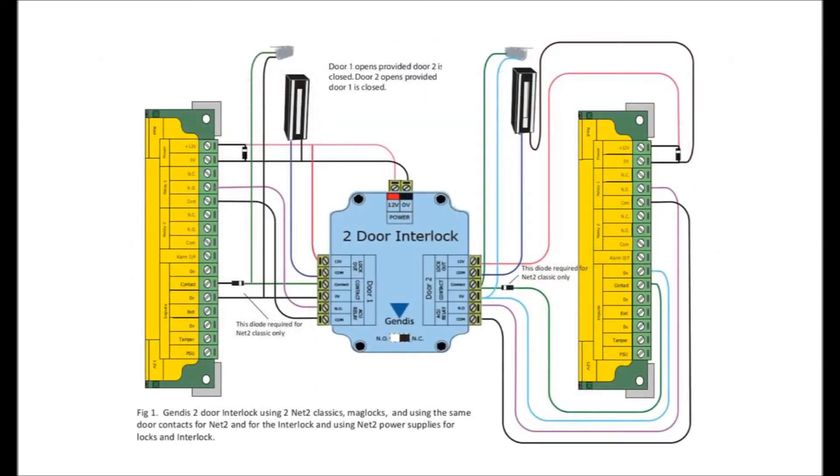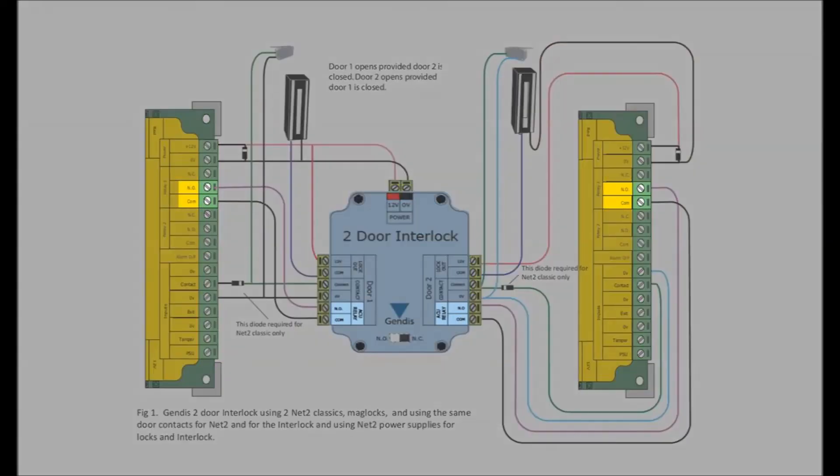When connecting the interlock device to a pair of Net 2 ACUs, you will need to connect the normally open and comm from the interlock to the ACU relay. So if you are using maglocks, don't connect the normally closed and comm from Net 2 to the interlock inputs. You should also place two diodes, one across each lock to protect the relay coil from any reverse electromotive force.